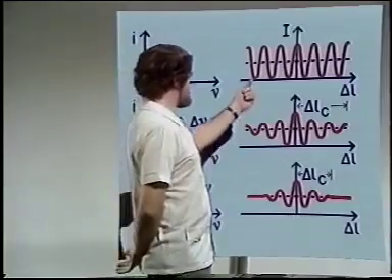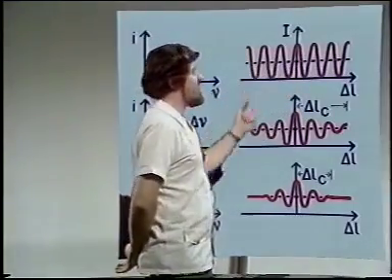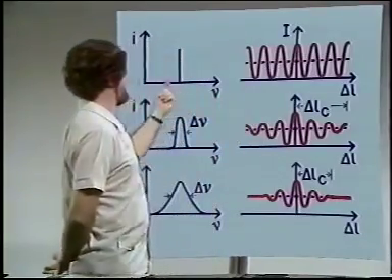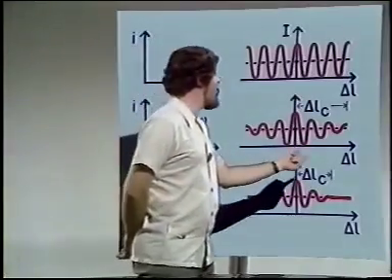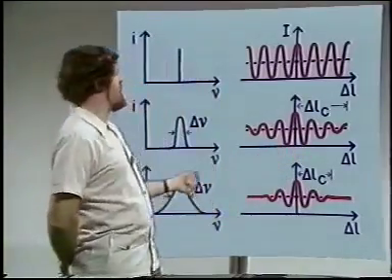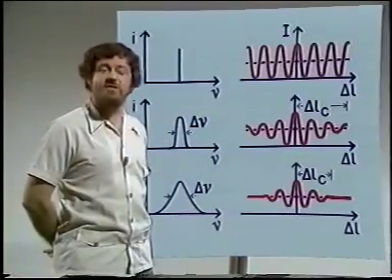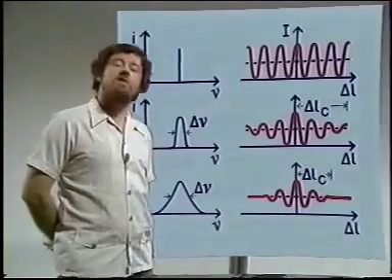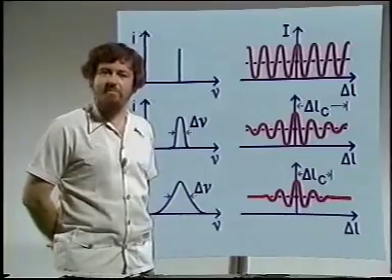If you look at this one here, we have cosinusoidal fringes oscillating around this dotted line. A cosinusoid, the Fourier transform of it, well, that's just a single frequency. There it is. And in fact, it's true in the general case. Given an interferogram, we can always, by means of a Fourier transform, establish all the details of the spectrum. And that's the basis of a very important technique called Fourier transform spectrometry. Well, now let's have a look to see how this technique is put to use to solve a practical problem.